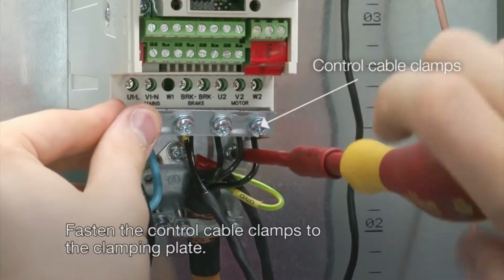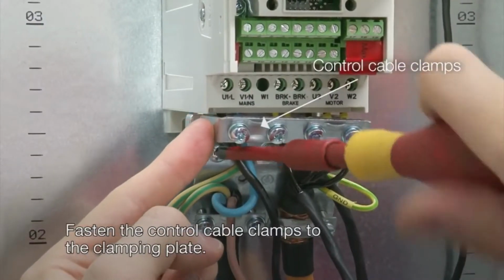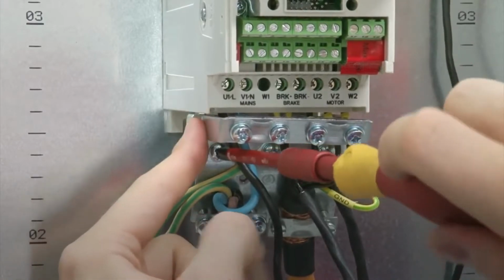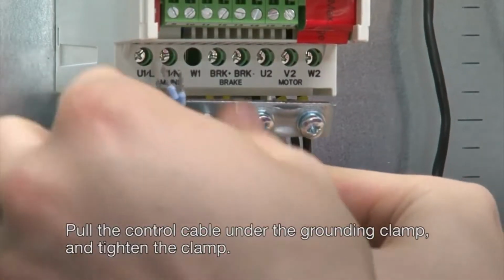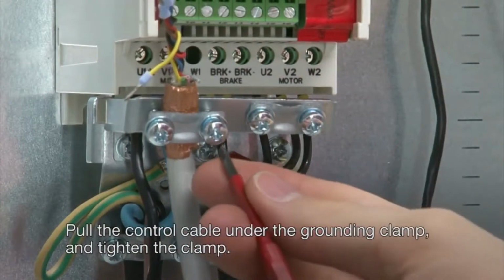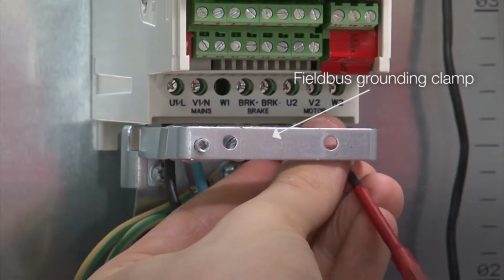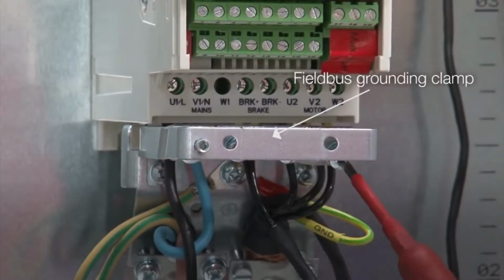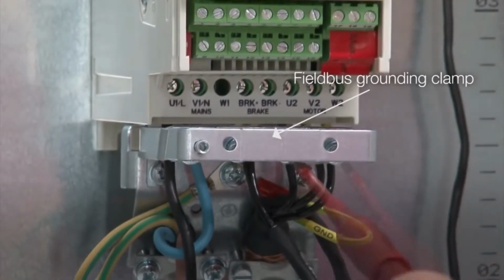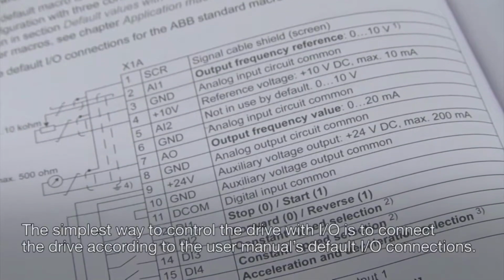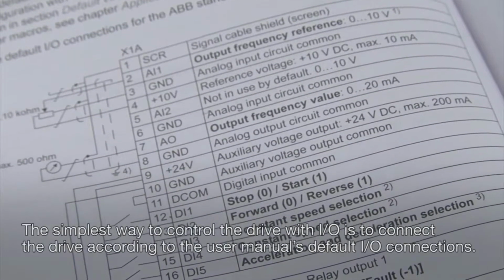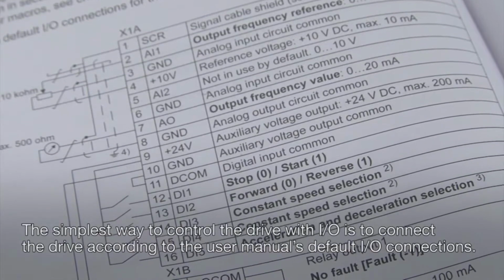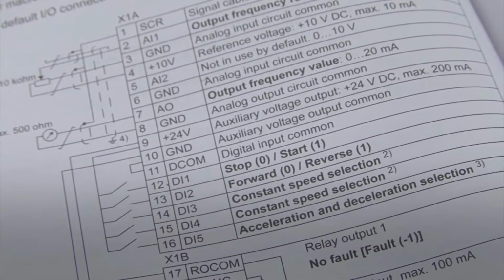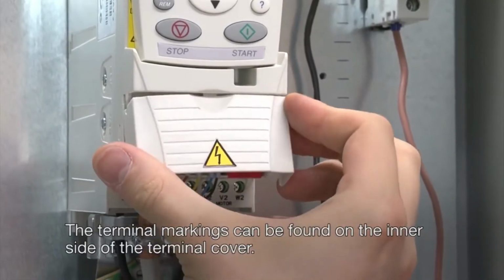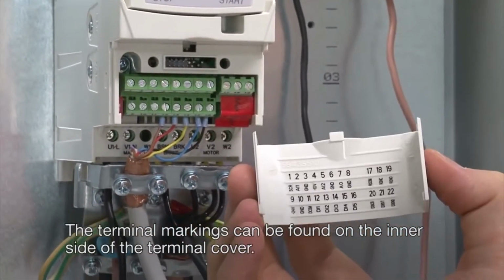Fasten the control cable clamps to the clamping plate. Pull the control cable under the grounding clamp and tighten the clamp. The simplest way to control the drive with I/O is to connect the drive according to the user manual's default I/O connections. The terminal markings can be found on the inner side of the terminal cover.